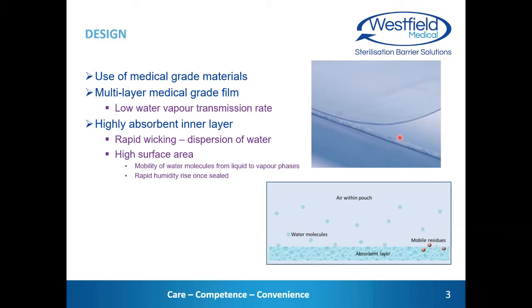The inner layer, which you can see here, is a highly absorbent material, but more significant for the purposes of HUMIPAK is that it has the ability to wick water molecules very rapidly across the surface. And what this does is give a very high surface area of water molecules on this material, which in turn allows for a very rapid increase of humidity inside the sealed pouch as these water molecules move from the liquid phase into the vapor phase. The recommended amount of water to use with each pouch covers around about 1/4 to 1/3 of the surface area of the pouch. This allows for further absorption capacity, so that if there are any wet residues on instruments, these can also be absorbed within this layer, and it means that there's no liquid residue there to run out when the pouch is opened.